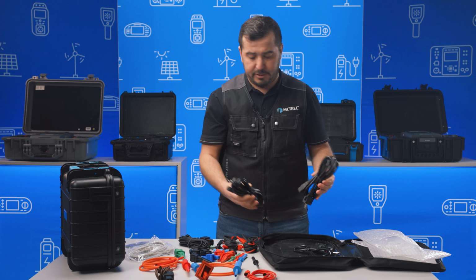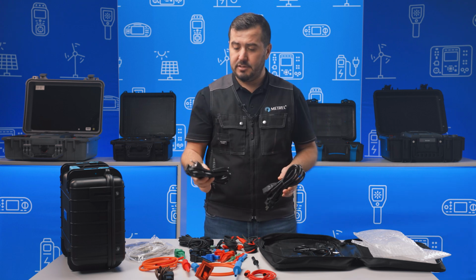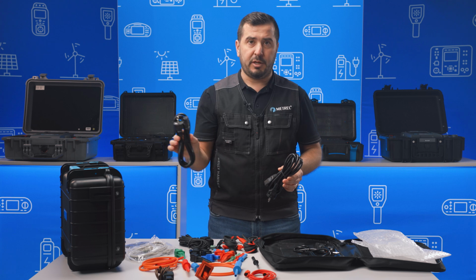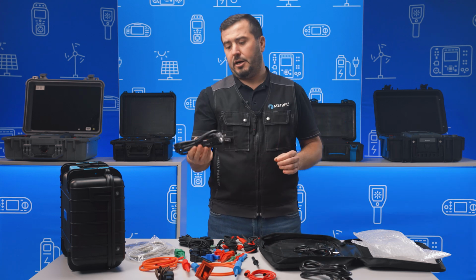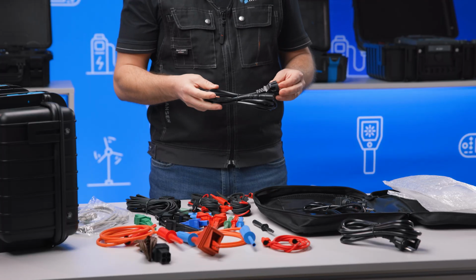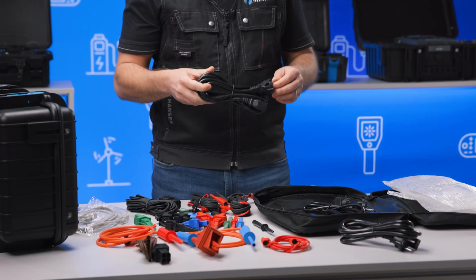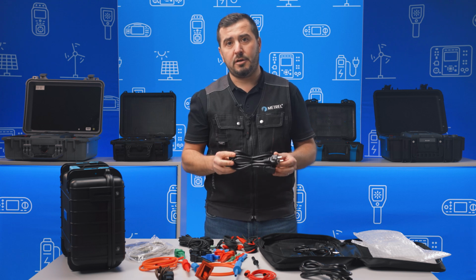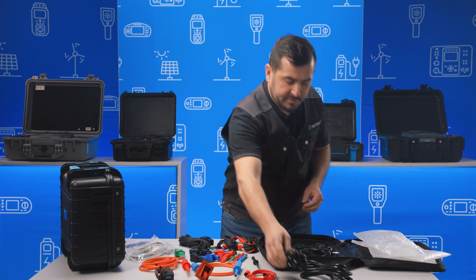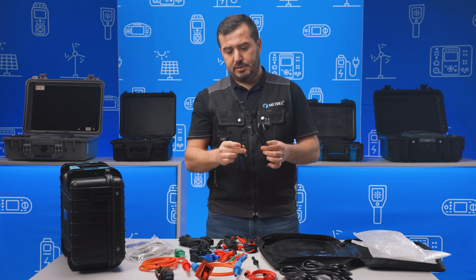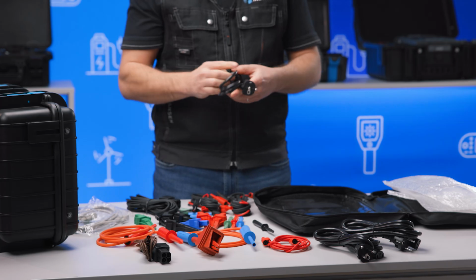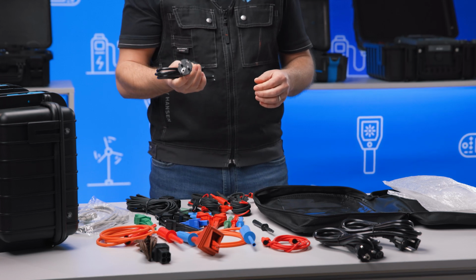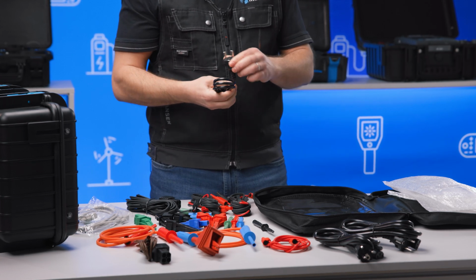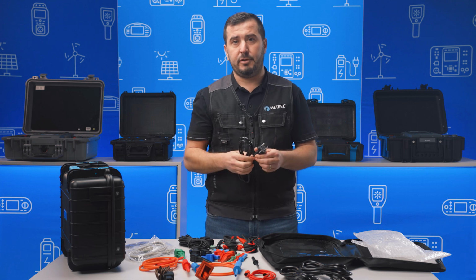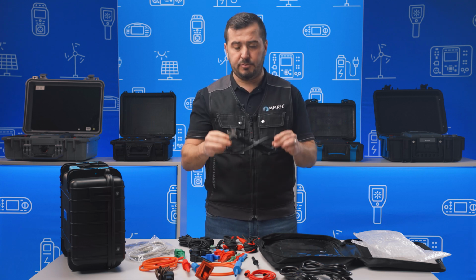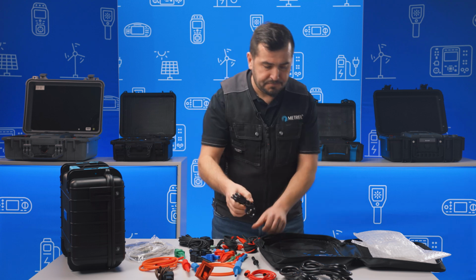Inside here we have two IEC leads. One is intended for the power supply of the instrument, and the other one can be used for testing extension leads that may also be RCD or PRCD protected. Then there is this special plug cable, which is designed again for testing safety of electrical installations, where we have sockets that we can test via this universal test cable.